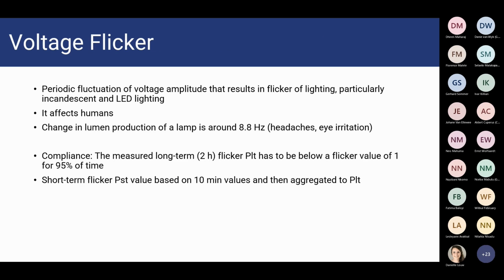All right, and then lastly, what also needs to be looked at for voltage waveform assessment is your voltage flicker. Voltage flicker is the periodic fluctuation of voltage amplitude that results in the flicker of lighting, particularly in incandescent and LED lighting. This flicker, a physical phenomenon that you can sometimes see, will affect people because there's a change in lumen production, normally close to around 8.8 hertz, which can lead to headaches, eye irritation, etc. I'm not sure if you've seen examples of that. If you get headaches at the end of the day, maybe you have a case of voltage flicker.